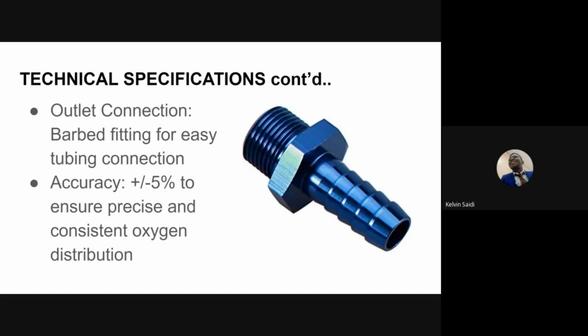When we are talking about the accuracy, most oxygen splitters boast an accuracy of plus or minus 5% of the labeled flow rate. This ensures precise and consistent oxygen distribution to each outlet port. So if you do this, you are meeting individual patient requirements accurately.